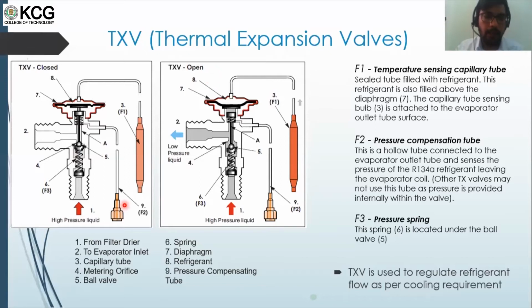Here I would like to tell this F2. This is the pressure compensation tube. This is what we call for TXV setting. So as I told, the TXV should close at 4 degrees Celsius. So how do we set the TXV exactly at this position? So this is done by this pressure compensation tube. And we can adjust the pressure inside this refrigerant by adjusting this, so that it will close the TXV exactly at 4 degrees Celsius.